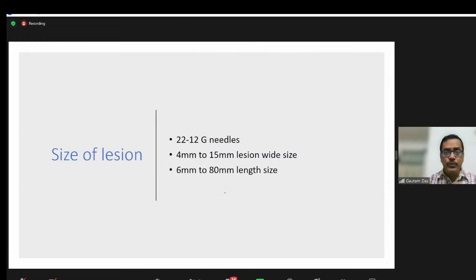But what is new in the cryo probe? Because cryoablation is not new, tumor ablation with cryo has been done for several decades. But what's new is the engineering mechanism, by which even with a 22 gauge probe - not needle, I'm making the mistake again, 22 gauge probe - there is an inner and outer tube through which the gas is passed. So this is new, meaning a very fine cryo probe has been developed, which gives you the flexibility of doing a very small size lesion, from 4 millimeters up to 80 millimeters.